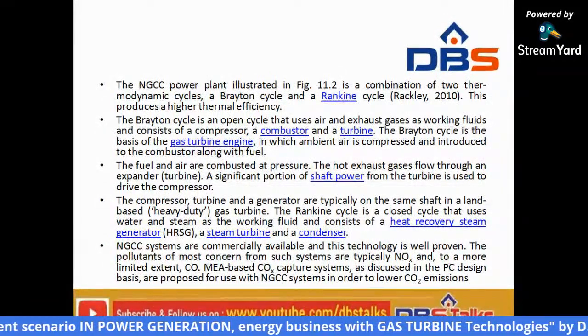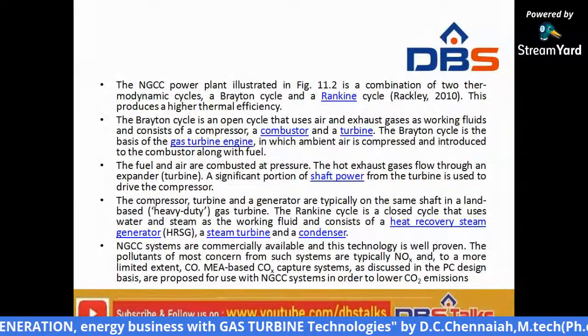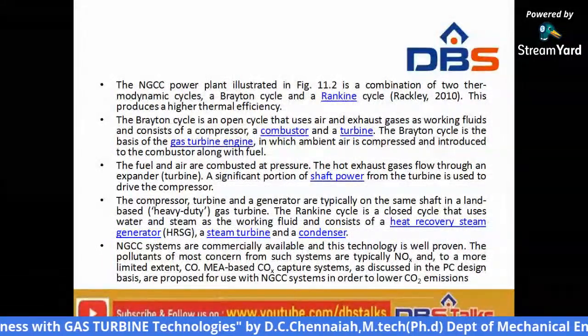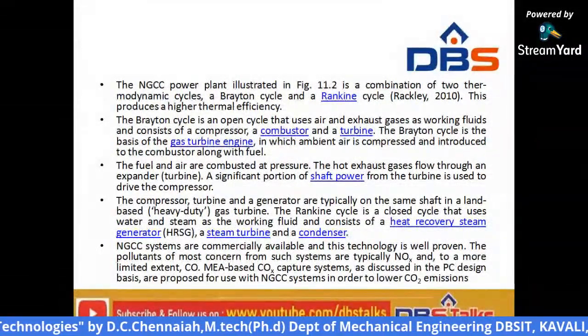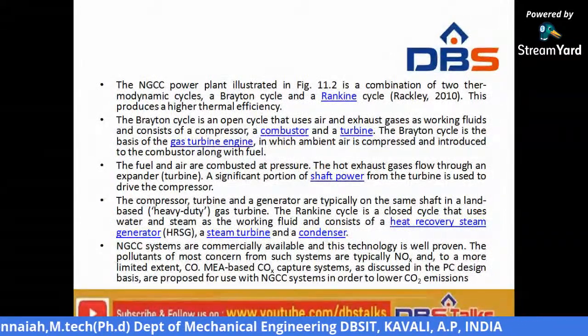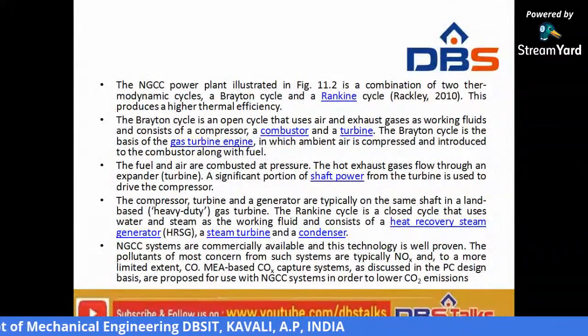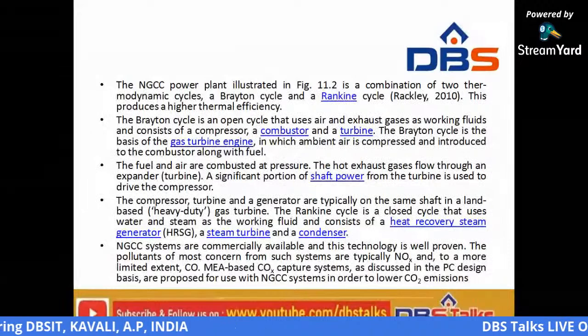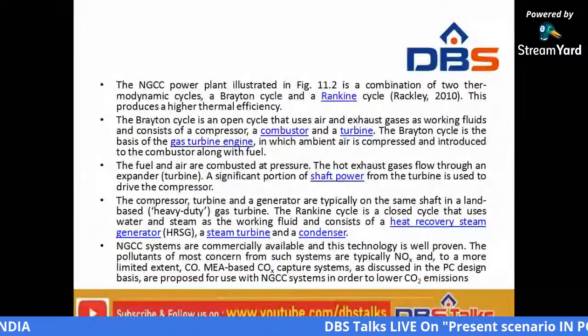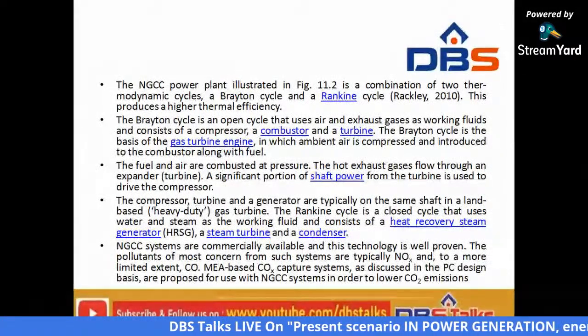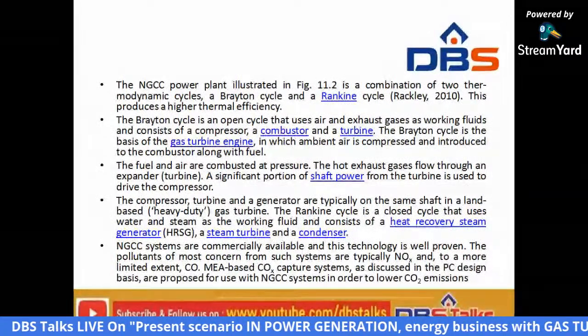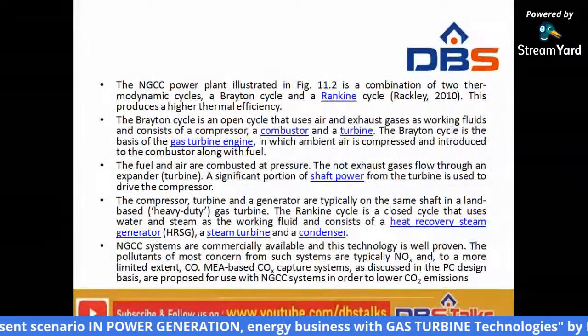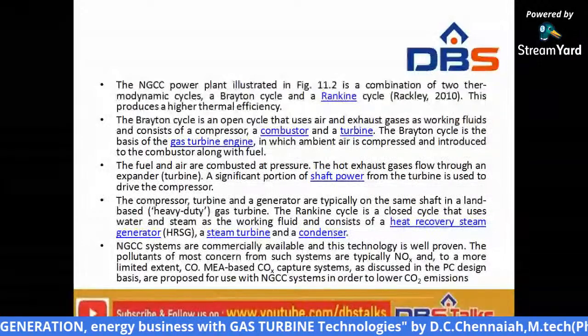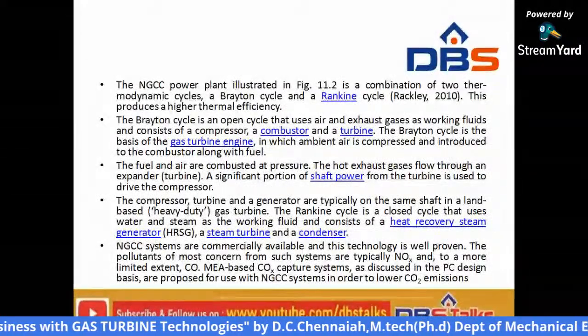The condensation is nothing but the steam. How does this condensation form in the condenser? The condenser is a heat exchanger. Cooling water supplied from a cooling tower is sprinkled or flows over the tubes through which steam is flowing. Because of the temperature difference, the steam rejects the latent heat of condensation to the cooling water.